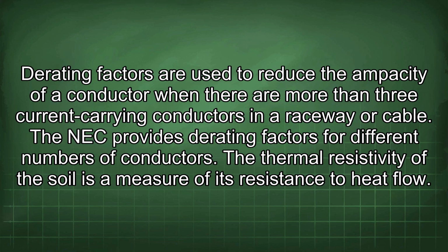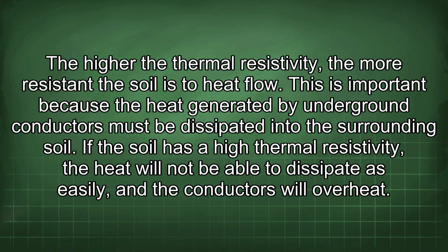The thermal resistivity of the soil is a measure of its resistance to heat flow. The higher the thermal resistivity, the more resistant the soil is to heat flow. This is important because the heat generated by underground conductors must be dissipated into the surrounding soil. If the soil has a high thermal resistivity, the heat will not be able to dissipate as easily, and the conductors will overheat.